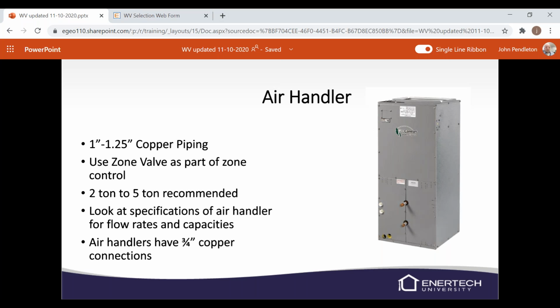There are 3/4 copper connections on the unit that are stubbed out, but we do recommend running either 1 inch or 1.25 inch copper piping to it and using the zone valve as part of the zone control. If you've got a call for your air handler, I'd run it through your zone valve. That way the zone valve opens before it actually gives a call to the unit, so we can make sure we've got water flow to it before we run that fan. We do recommend that you stick to between 2 and 5 tons. With the buffer tank package, you can go down to smaller air handlers, but you will have to have a buffer tank if it's smaller than 2 tons.